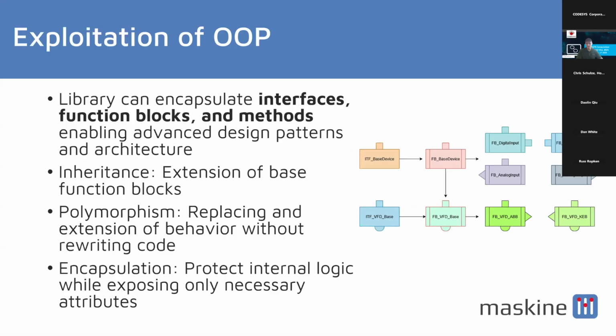The best example of this is going to be VFDs, right? For the most part, VFDs behave the same regardless of manufacturer, at least on a base level. They're going to have a command to move forward and backwards. They'll have a speed set point and a speed feedback. There's probably going to be some error handling for speed timeouts, for a motor stall, maybe some current monitoring. And typically it's going to have a control and a status word. But that control and status word is going to differ from manufacturer to manufacturer.